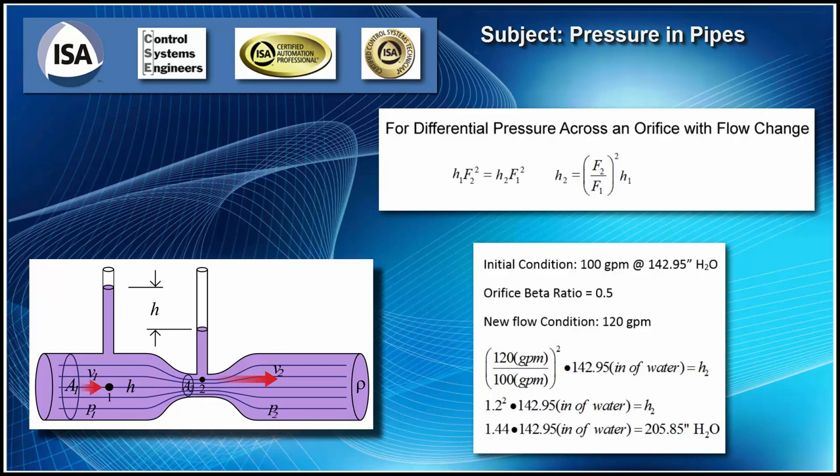One other important note is, notice that if we put a valve on the end of the piping system, and we shut that valve and deadhead it, again we have Pascal's law, and the pressure is the same anywhere in the system because it's a pressurized system where there's no flow. So when there's no flow and you're deadheaded, the pressure is the same everywhere. When you open the valve and you start flowing, that's when our static pressure starts dropping proportional to the flow, because we're giving up energy to overcome the resistance and push the water.